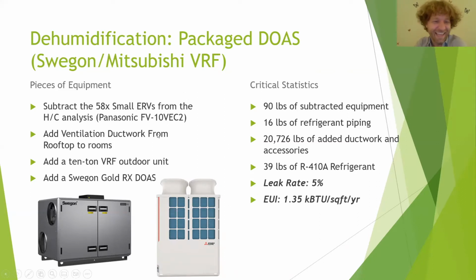We split apart the dedicated outside air system into two pieces. Usually a VRF unit is connected to a DX coil attached to this unit, and it does the dehumidification process using a VRF system. There's some field-installed equipment, so it's a little harder to install and there's a possibility of more leaks. It's not a lot more refrigerant, but it is a bit more. But these systems perform really well at low temperatures, whereas packaged systems aren't as good. So as it gets colder, these become better and better than the package systems.